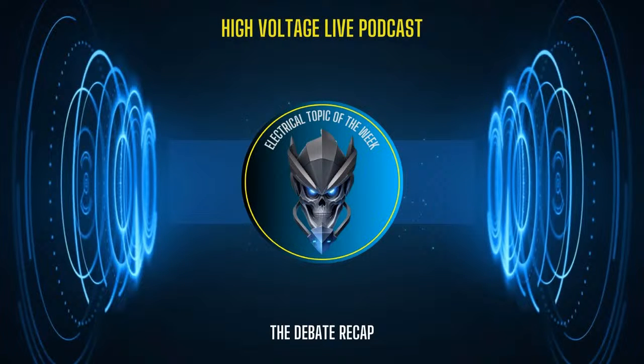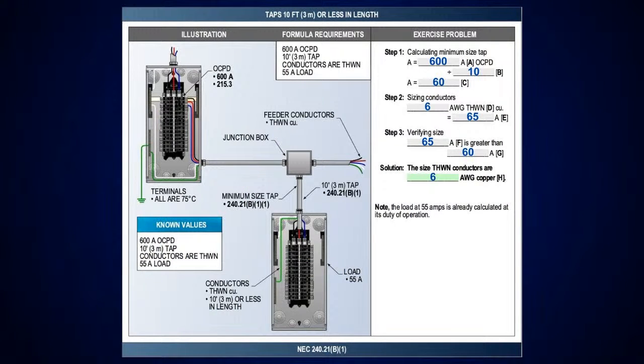All right. We're right back into what we were doing last week. We're just continuing on. We're calculating conductor ampacities. Last week we got into talking about doing the taps, and like this one here, we're in 240.21(B)(1). And as I said, and I'll rephrase this one more time, if you're doing a tap that's 10 foot or less, you divide by 10. All other taps that are greater than 10 foot, you take at a third. And if you have a transformer and a tap, you do the secondary to a third, or the primary to a third, but when you get to the secondary, you're going to take it at a third, but you also need the ratio of the transformer, okay? Sure. So we'll go through this real quick. This shouldn't take long.